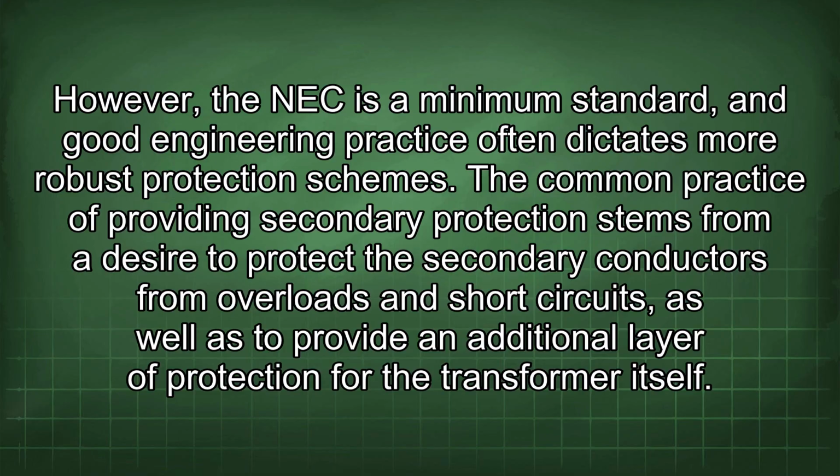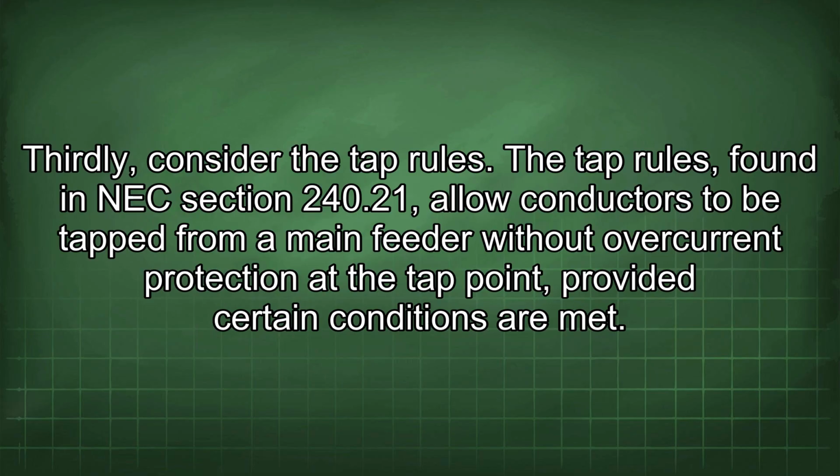The common practice of providing secondary protection stems from a desire to protect the secondary conductors from overloads and short circuits, as well as to provide an additional layer of protection for the transformer itself. Thirdly, consider the tap rules.